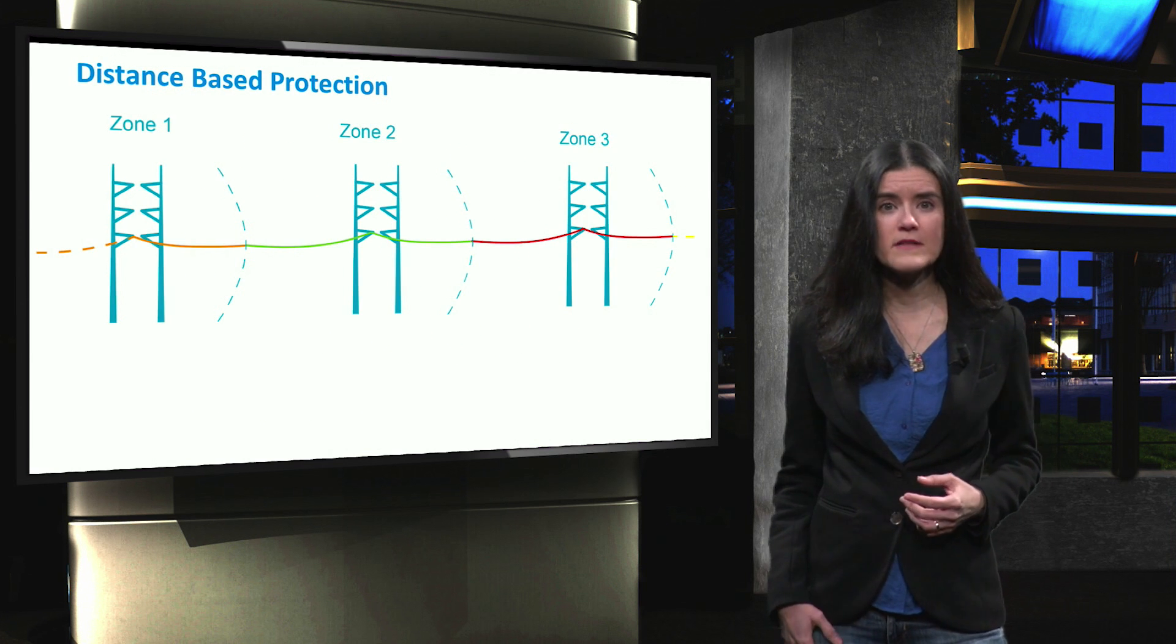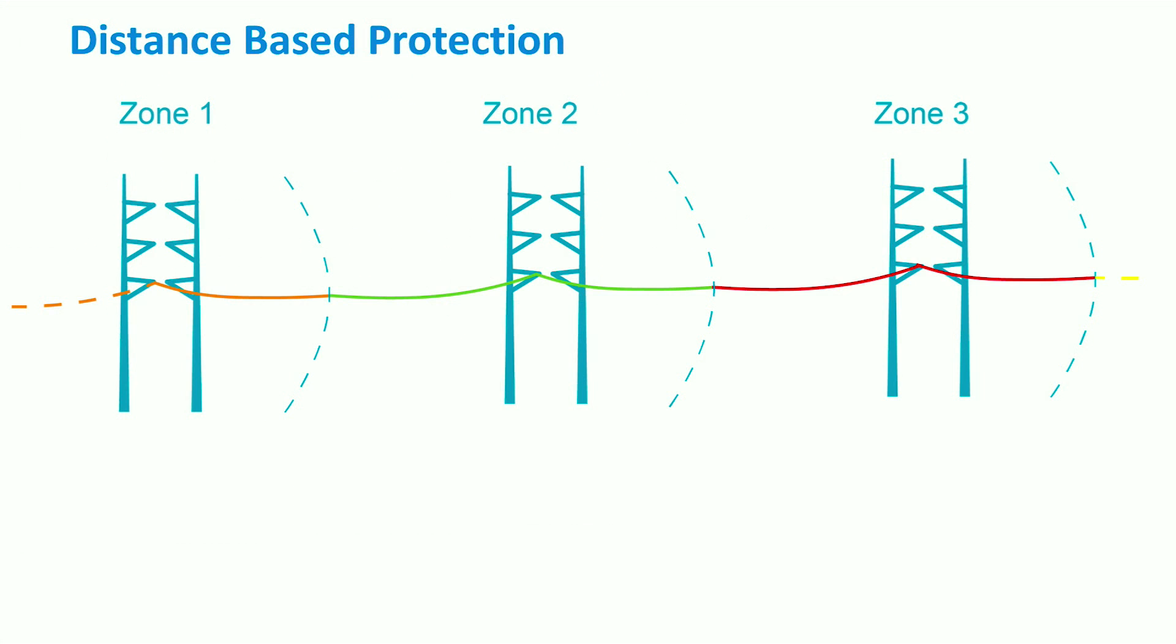Let's now look at the distance-based protection method. Distance protection relies on the use of distance relays, where the current and voltage at the relay location are compared. Based on the measured values of current and voltage, the relay calculates the impedance at its location.